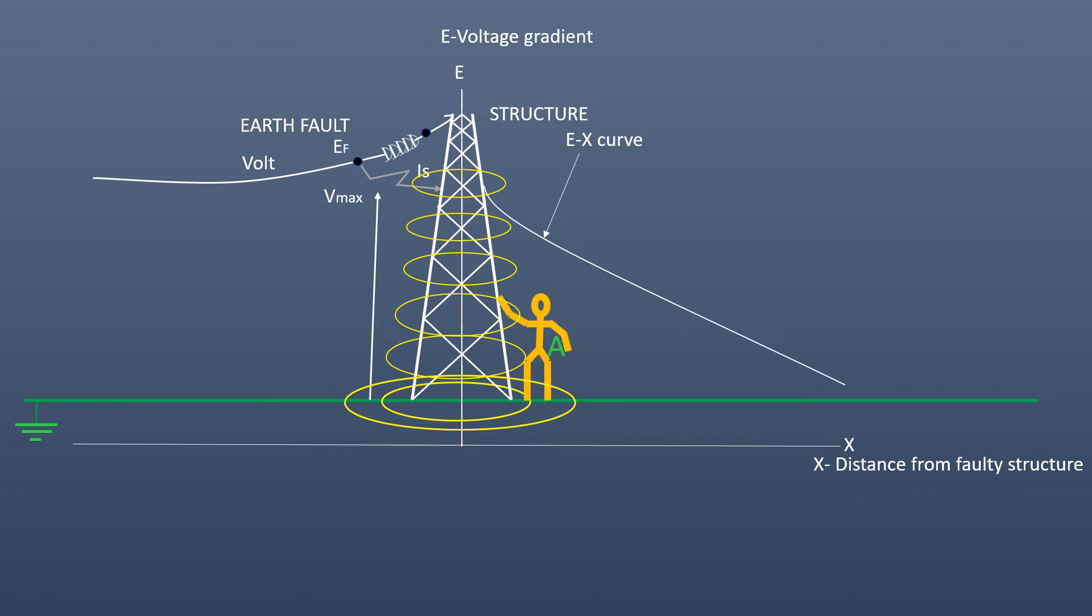Suppose a person standing on the floor of the substation touches the fault structure by raising his finger. Voltage at touch point is Va and voltage at his feet is Vb. A voltage or potential difference Va minus Vb causes a flow of current through his body which offers him electrical shock. Here Va minus Vb is the touch potential.